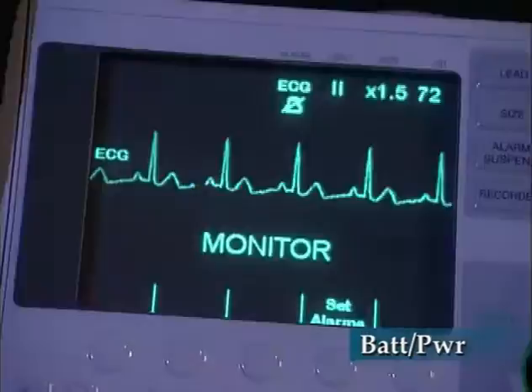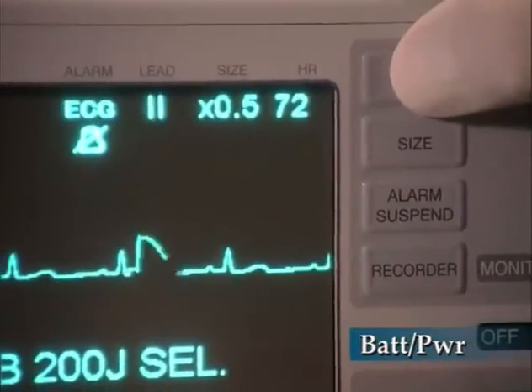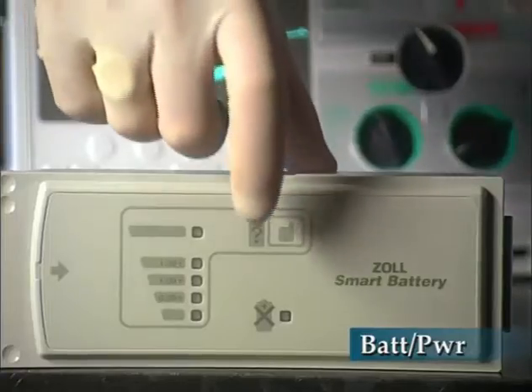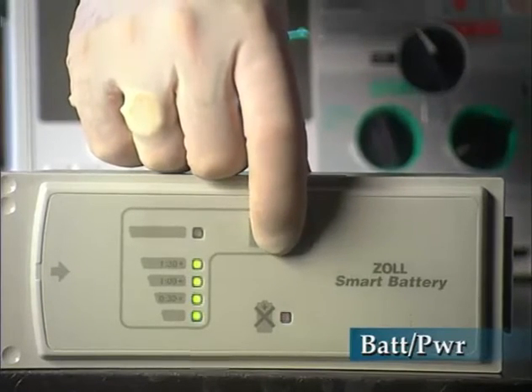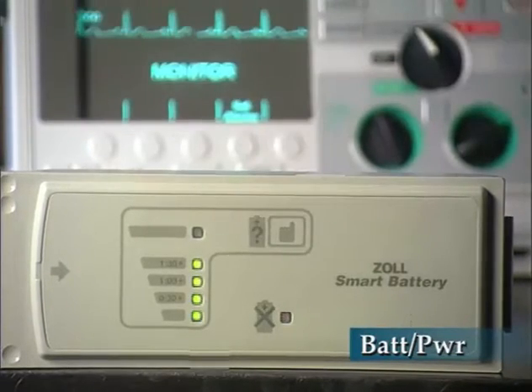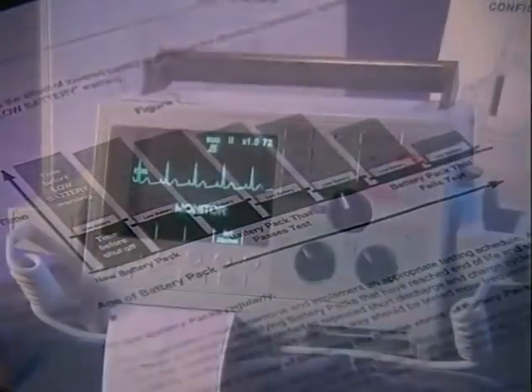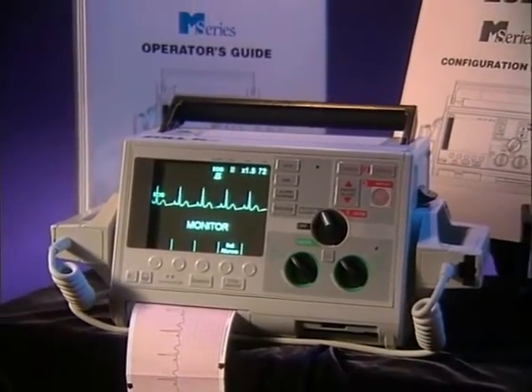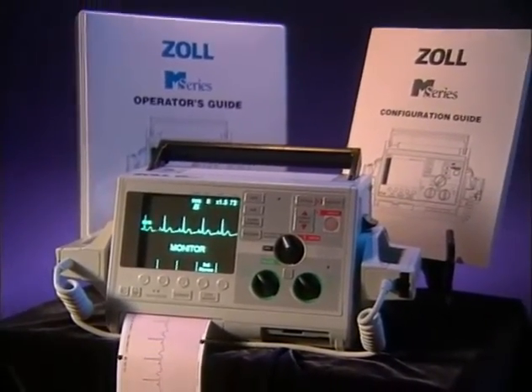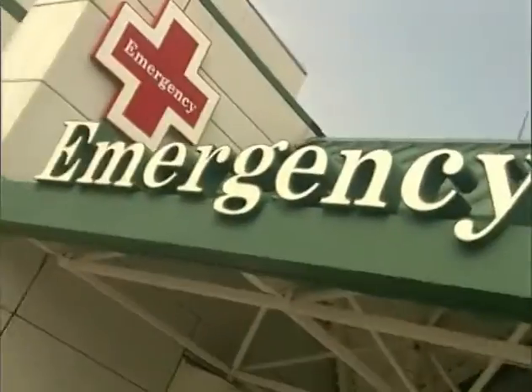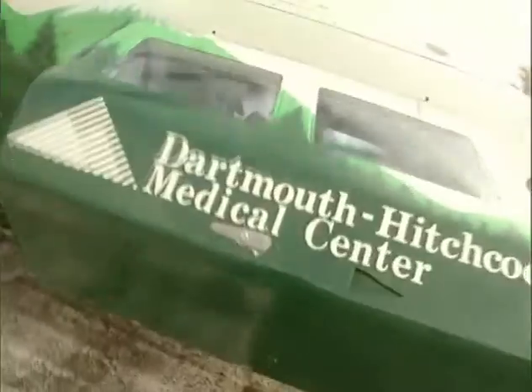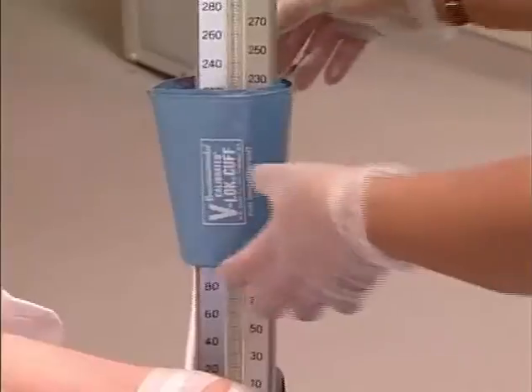The number of batteries used, frequency of use, and how they are used affect capacity. Because of this, ZOLL recommends periodic testing and that you replace batteries on a preventative, scheduled basis, or at least every 18 months. Please review your operator's guide for other important steps in managing batteries. Before using the ZOLL M Series, we urge you to thoroughly examine the unit and all associated materials. Additionally, using the M Series in a simulated cardiac arrest with ZOLL training electrodes and simulator will prepare you to use this equipment in emergency situations.